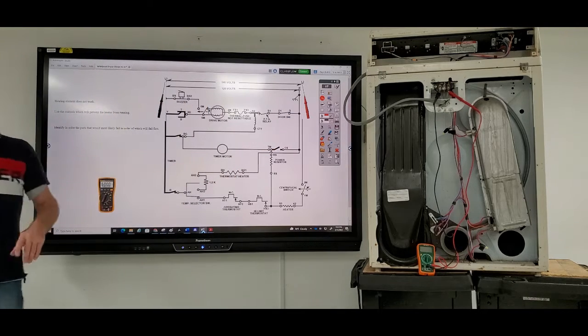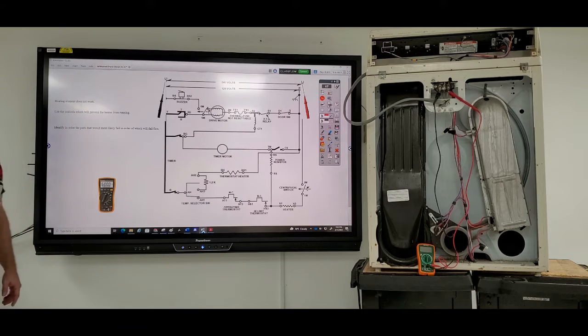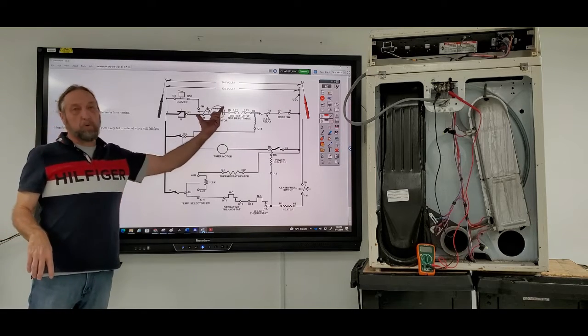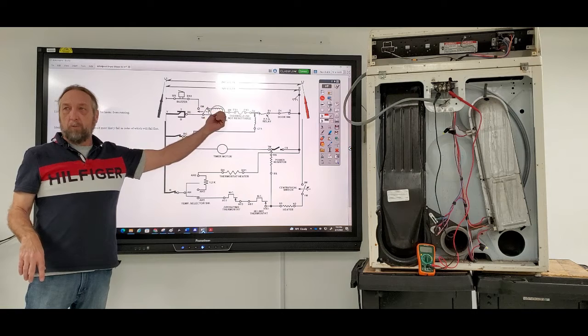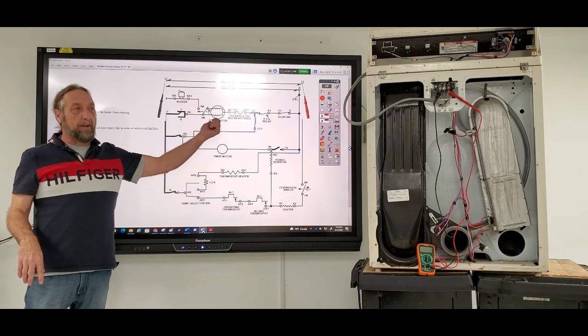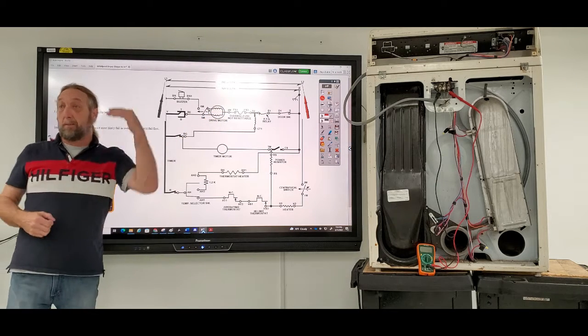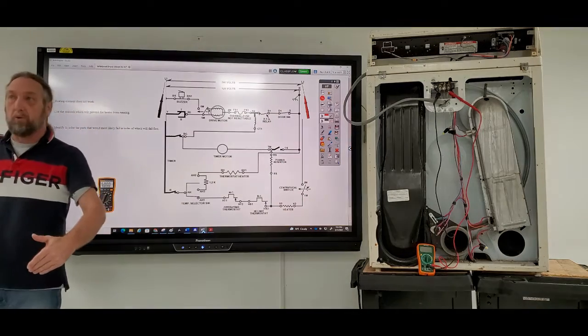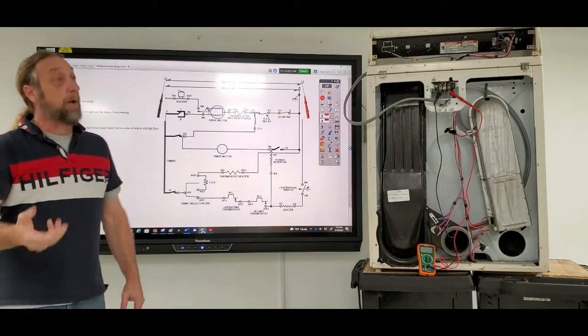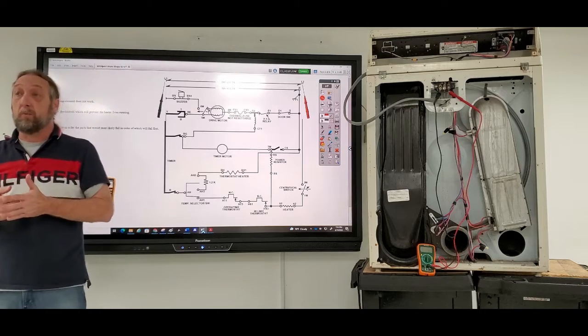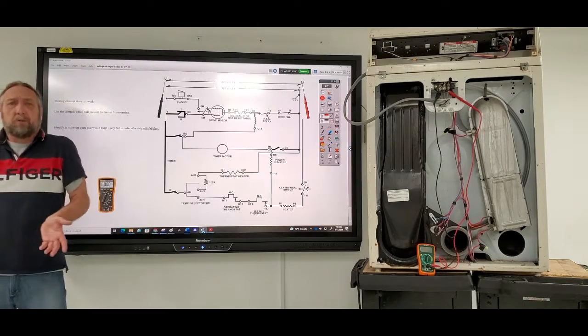Now, in a competition, let's go back to the motor for a second. You can say the motor's bad, but if you can ohm out the overload or ohm out the windings and be specific—say it's a bad run winding or a bad overload—the judge is going to give you extra points because you knew exactly what it was. Otherwise you're like, yeah, but I said it was the motor, I knew it was the motor.